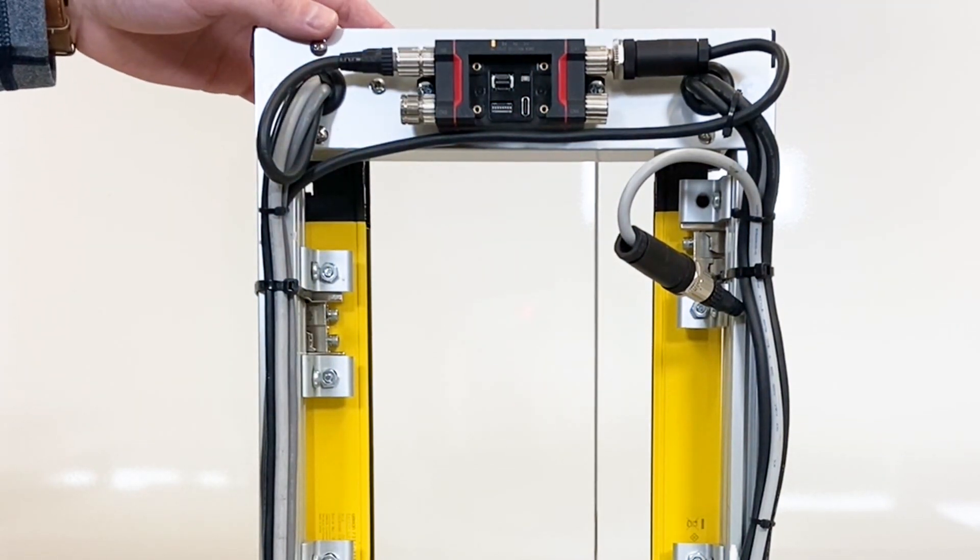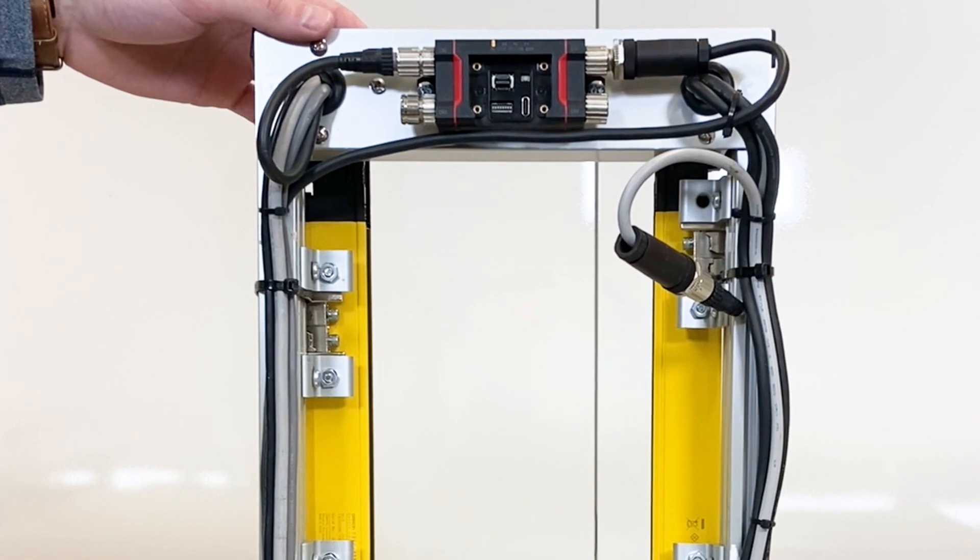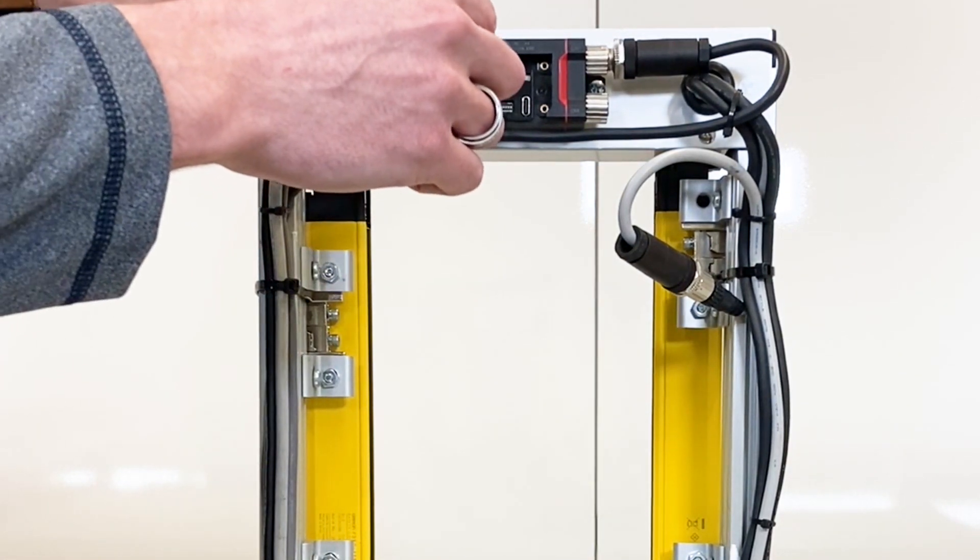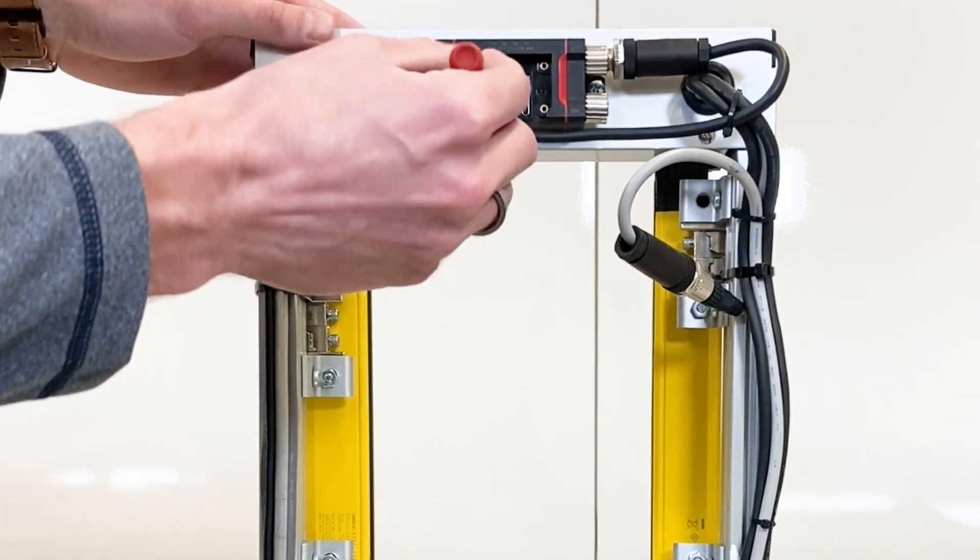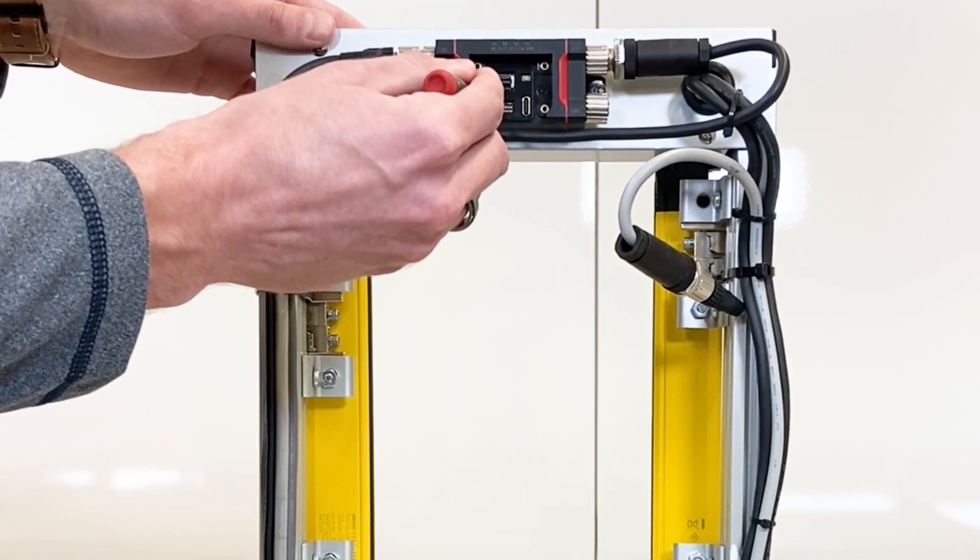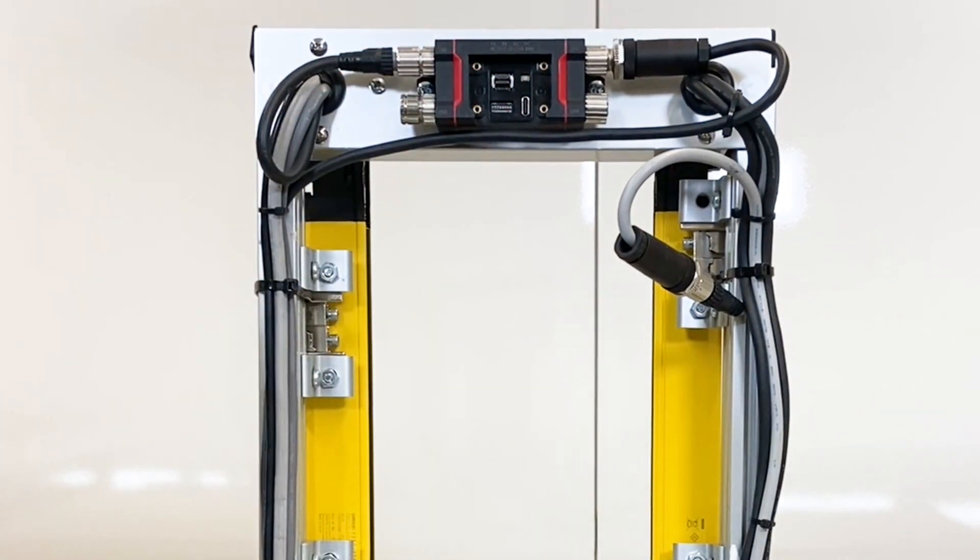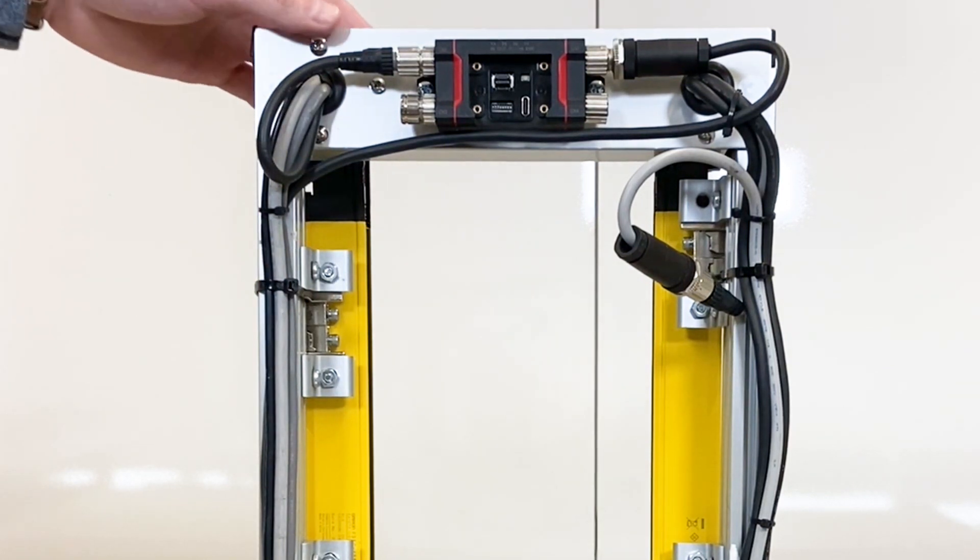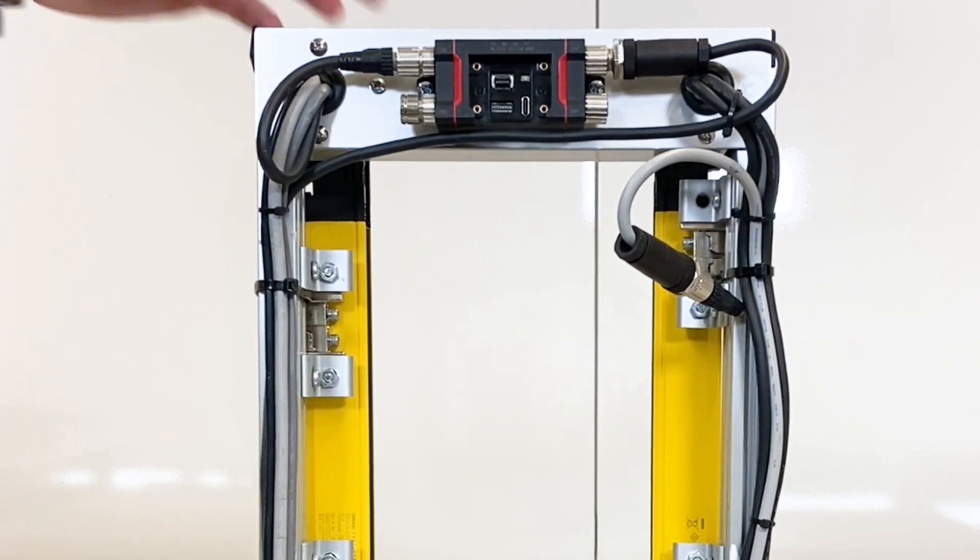From here, what you want to do is power your safety light curtain off. And then you will want to set the DIP switches to your desired programming, which is DIP switches 1, 2, and 3 in the on position. Once they're in the right position, what you want to do is power your light curtain back on. And everything will be programmed properly.